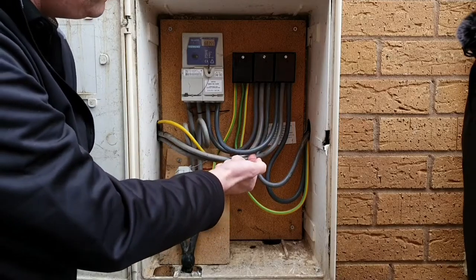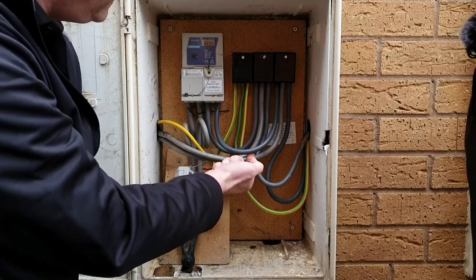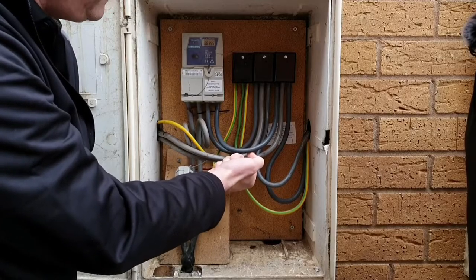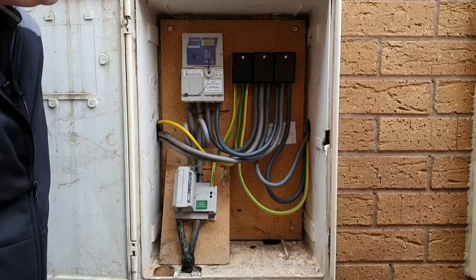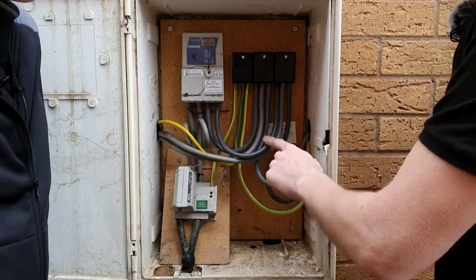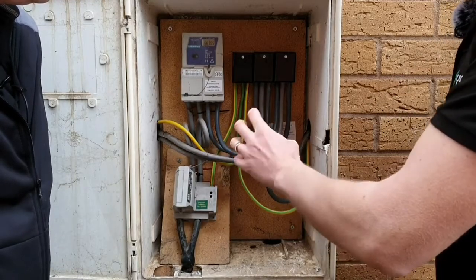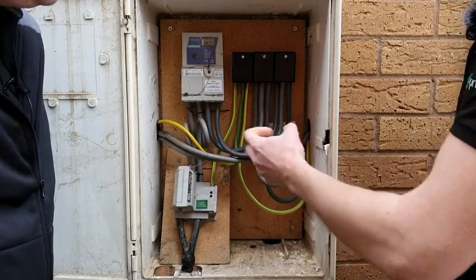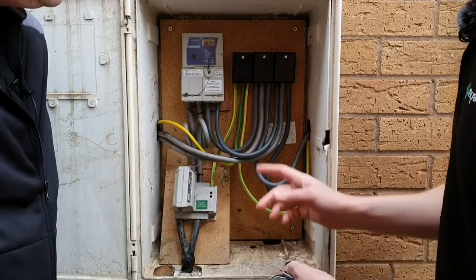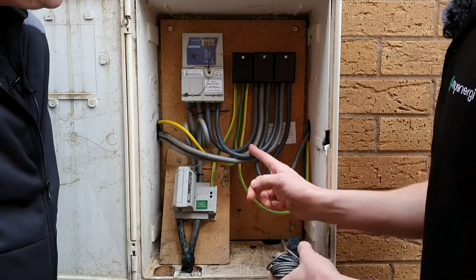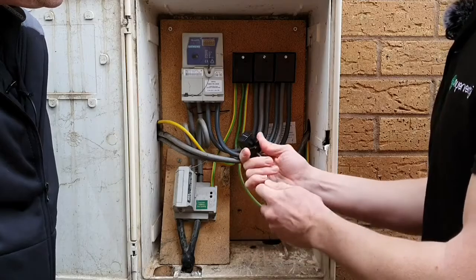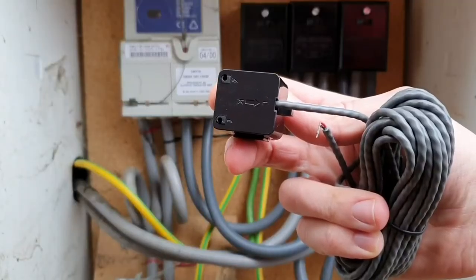And it's quite important, Joe, that we left this line conductor from the kilowatt hour meter of a reasonable length. What's the thinking behind that? Well, we've installed that deliberately at the very front of all of the other tails because we know these can get a little bit stiff when there's a lot of them in place, and it can get a little bit tricky to access them. But this is the one that we really need to access because that is where we're going to install our CT, our current transformer.